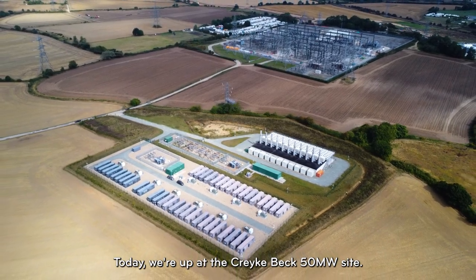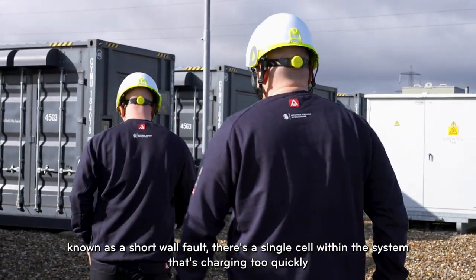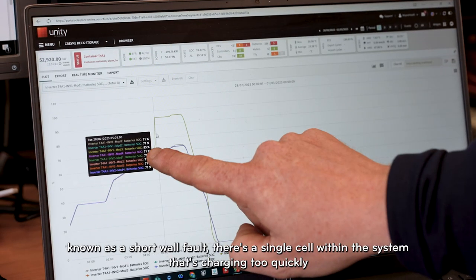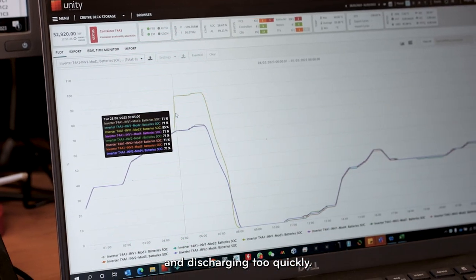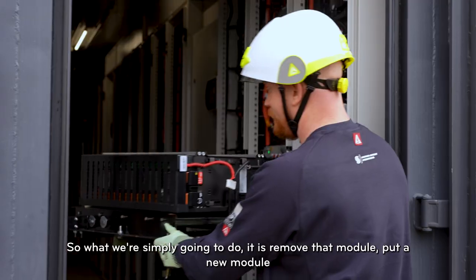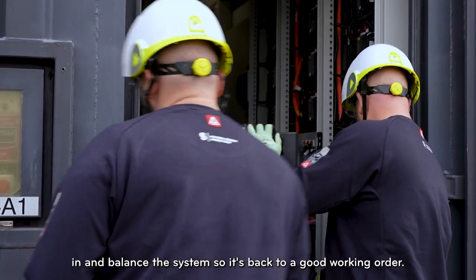Today we're up at the Creyke Beck, the 50 megawatt site. We've had an issue with a battery module because there's a short cell. There's a single cell within the system that's charging too quickly and discharging too quickly. So what we're simply going to do is remove that module, put a new module in and balance the system so it's back to good working order.